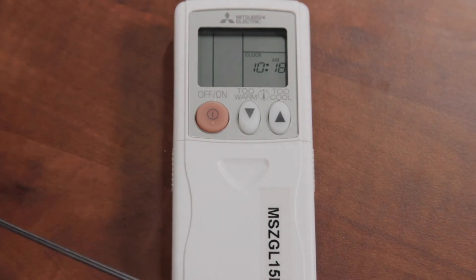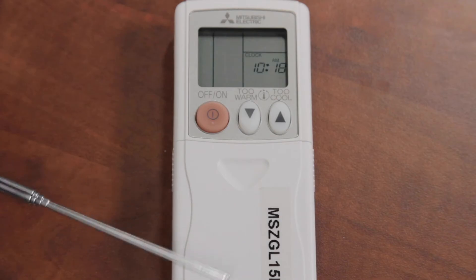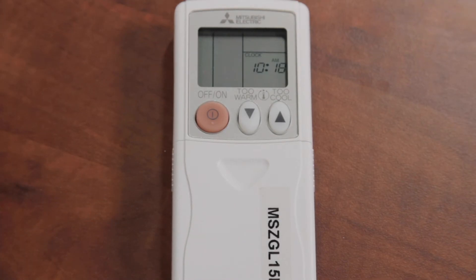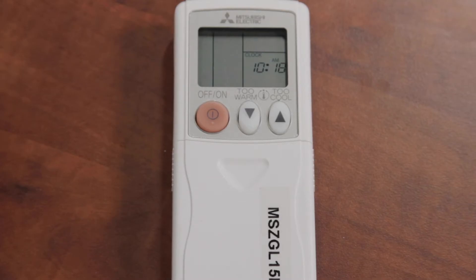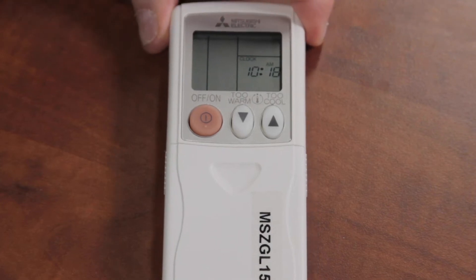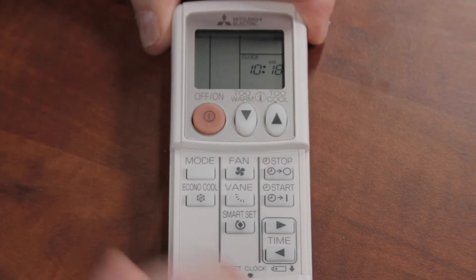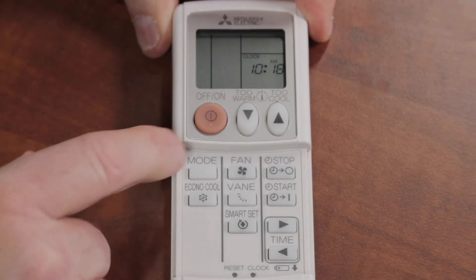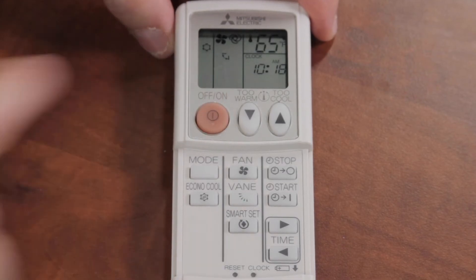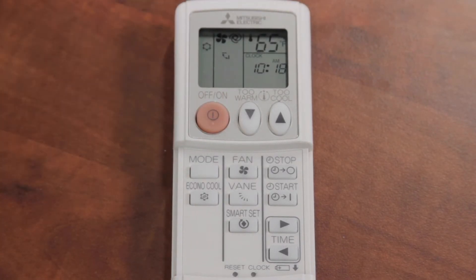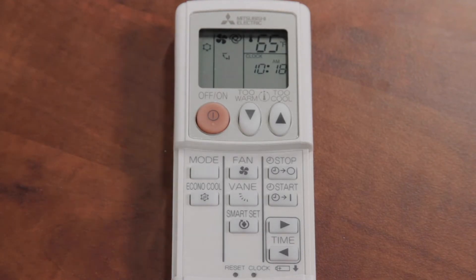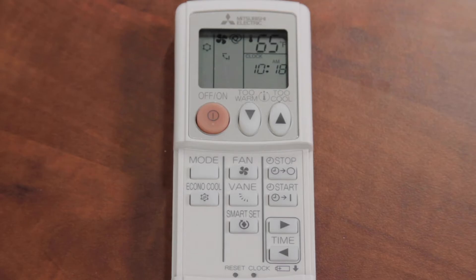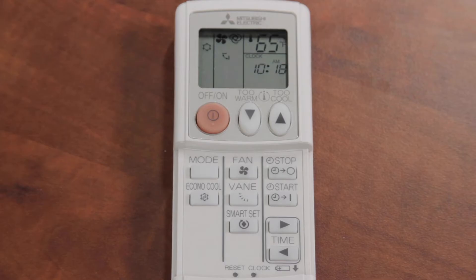I'm going to talk to you today a little bit about some of the advanced features and some of the types of phone calls that we get into the office sometimes that we like to help people out with before we go out and run a service. One of the big things that happens a lot of times with this particular remote control is on multi-zone systems where the customer calls in and says that we have one unit running in the cooling mode and one unit running in the heating mode and one unit's turning off, one unit's turning on. We have green lights flashing and blinking on our indoor units.